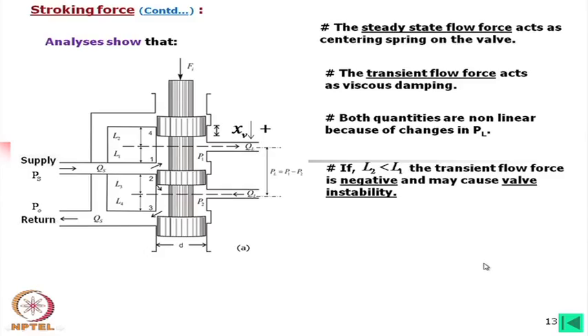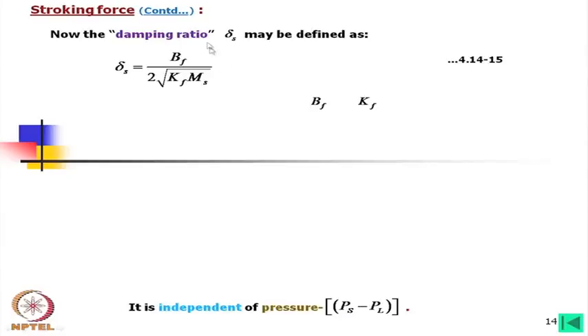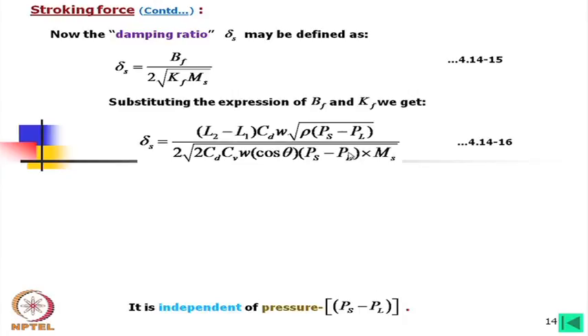A compromise is needed: usually L2 is taken slightly greater than L1. In design, it is maintained that L2 is either equal to or greater than L1. In normal practice, L2 slightly greater than L1 is preferred for positive damping while maintaining control of the flow force.